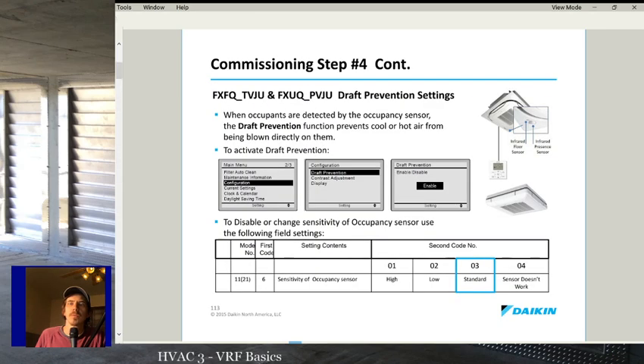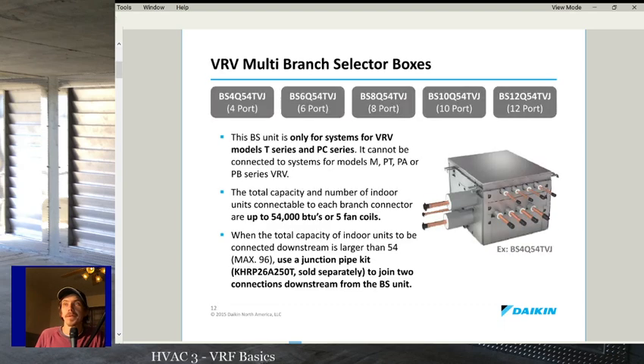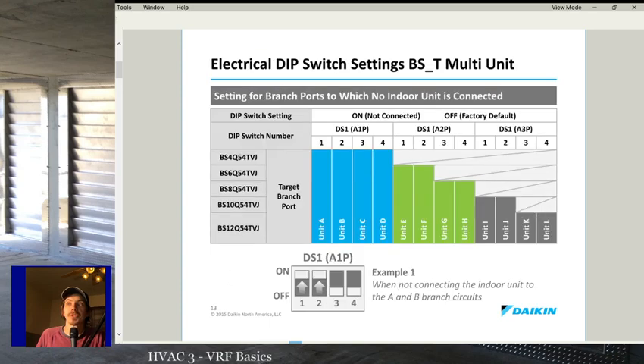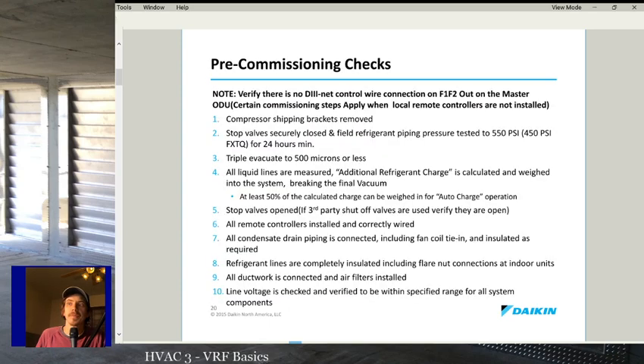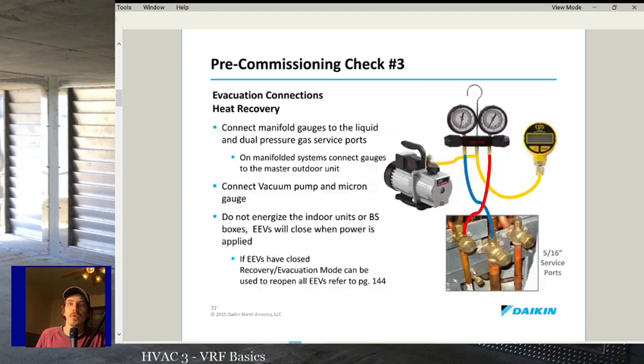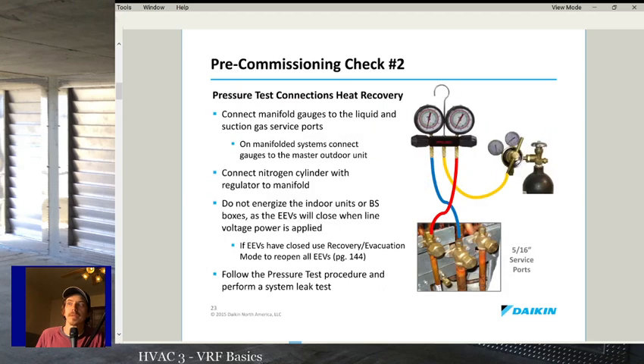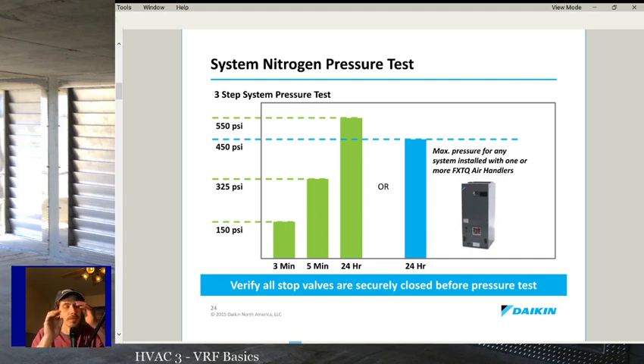So number one is, after you've got everything hooked up, well, first off, installing piping. When installing refrigerant piping, you should always purge with nitrogen. We'll get to vacuum in a minute. Let's talk about piping installation real quick. You should always purge with nitrogen. On small systems, you can get away with not purging and you'll have minimal problems.